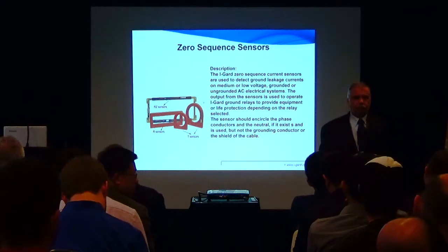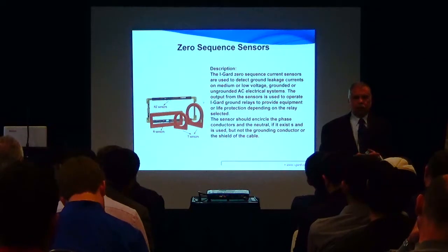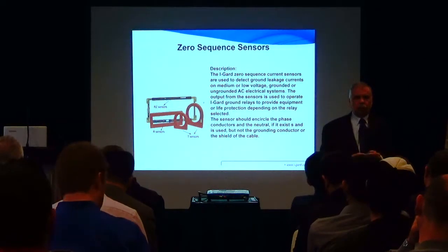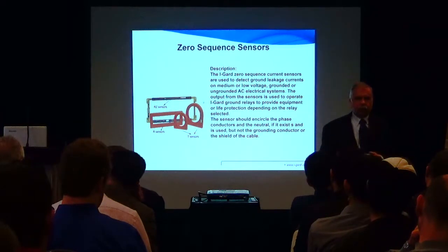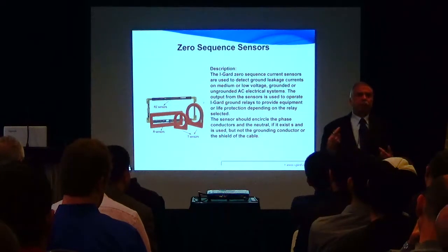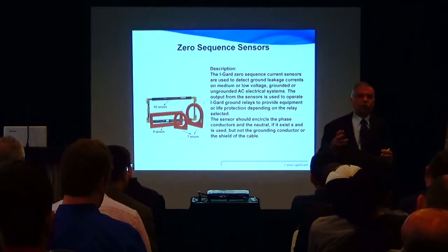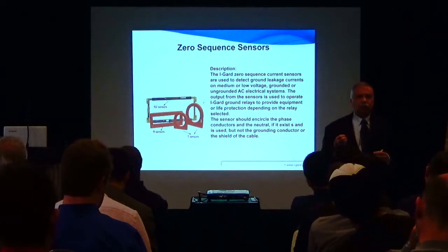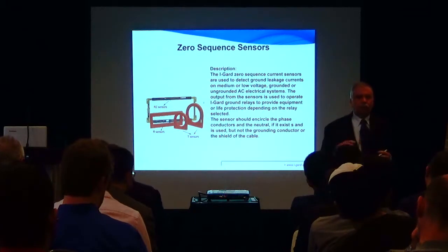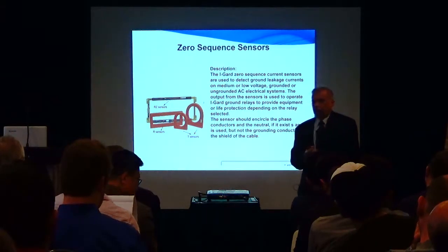This one is actually a little more cost than the normal device, the normal way of sensing the neutral current. This is more sensitive, and more cost. It has a high permeability core, a strip of high permeability core material to produce a sensitive output, with lots of flux for minimum excitation. Mu is very high, and then there is the cost of the winding, a large number of turns. So there is a cost associated with that, right?